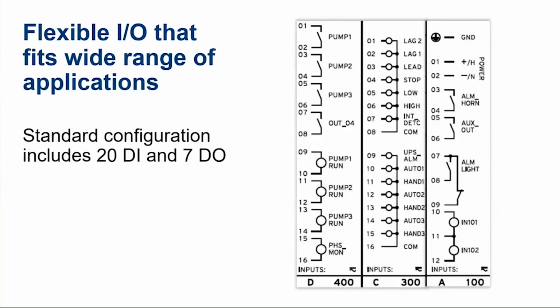The first 3 cards I'm going to show you are the digital input and digital output cards for controlling a lift station with just float switches. In slot C, as in Charlie, you can see the lag 2, lag 1, lead, all your float switches come into that card, as well as your hand-off-auto switches down towards the bottom. The nice thing about these different cards and that strategy is I can pick my voltage for each individual card. For my C card, I can use 24-volt digital inputs or 120-volt digital inputs. I don't have to put an interposing relay in there to get all the voltages the same within my panel, and that eliminates another point of failure in the enclosure with the controller.